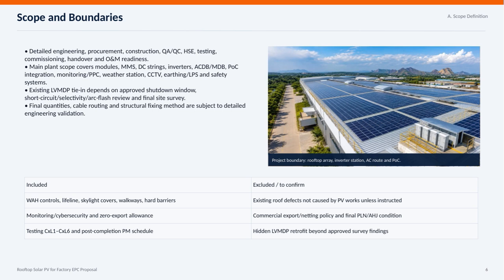The connection to the existing low-voltage main distribution panel depends on an approved shutdown window and thorough electrical reviews including short circuit, selectivity, and arc flash assessments, as well as a final site survey. Final quantities, cable routing, and structural fixing methods will be confirmed during detailed engineering. We also have clear inclusions like walkway safety features, monitoring and cybersecurity, and comprehensive testing and maintenance schedules.